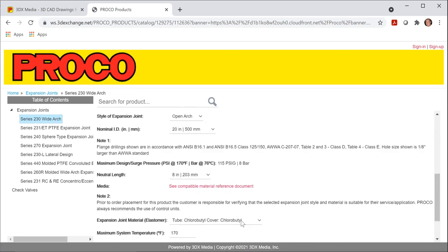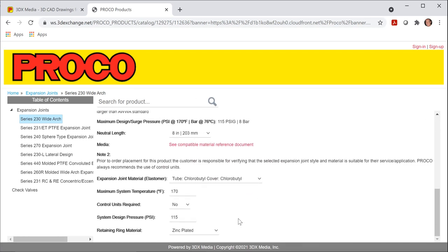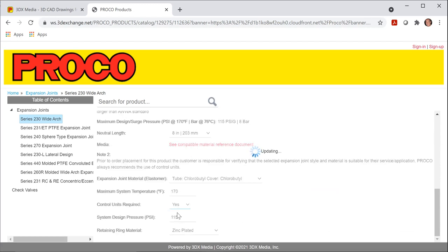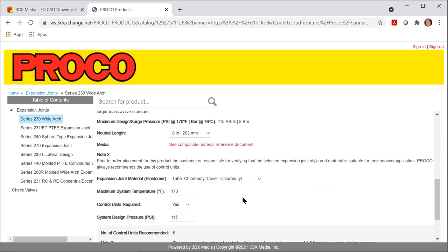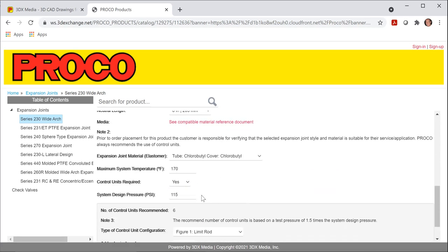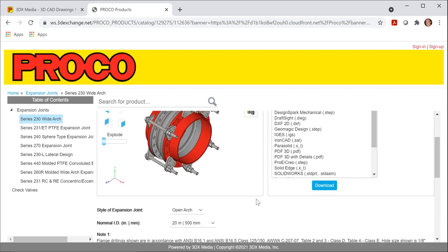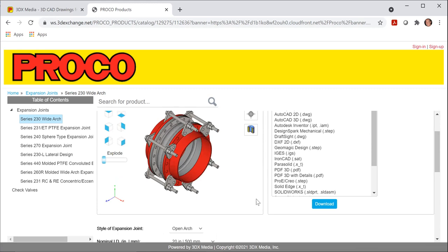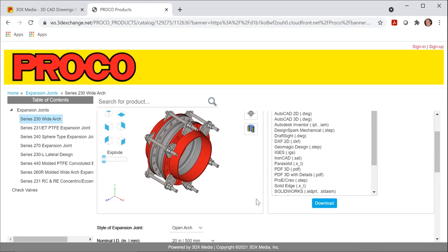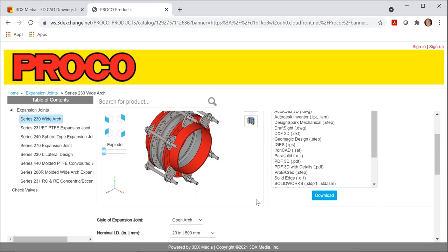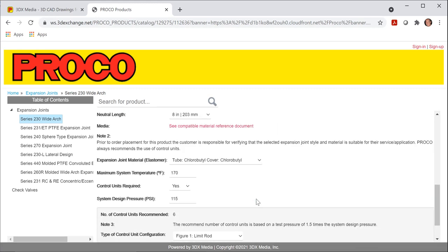I do want to have them available, though, and I'll show you why, so we'll re-select control units. Right now at 115 PSI, six control units are required, so we'll scroll back. You can see six control units are on the outside of the expansion joint.